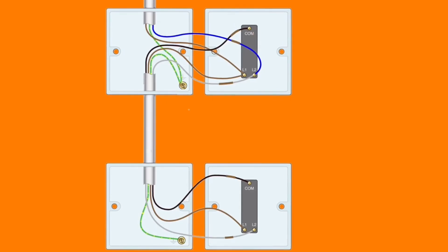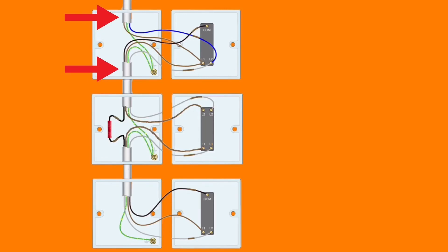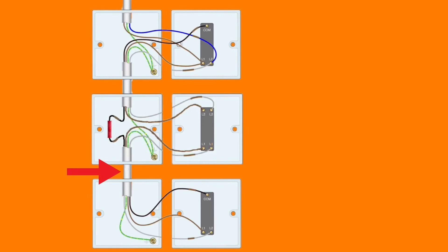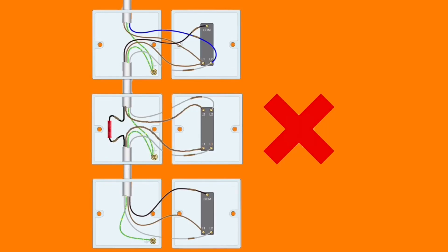In the final part of this presentation we're going to look at how we could introduce a third switch, making the switching arrangement two-way and intermediate. For two-way and intermediate switching, we've added a switch in the center. The top switch is still fed with a twin and CPC cable and still has a three-core and CPC going on to the next switch position, and is still a two-way switch. The three-core feeds into the second switch position, and we've added another three-core cable from that position down to the new switch position at the bottom, replacing the center switch with an intermediate switch.